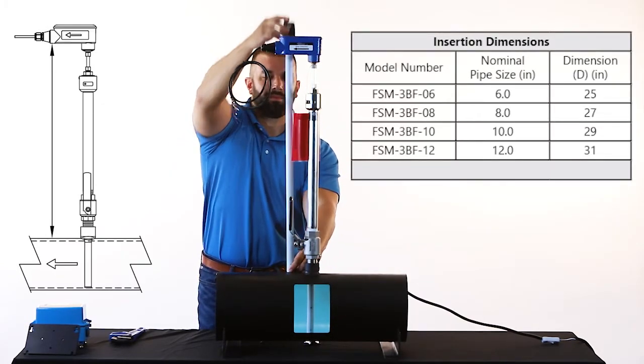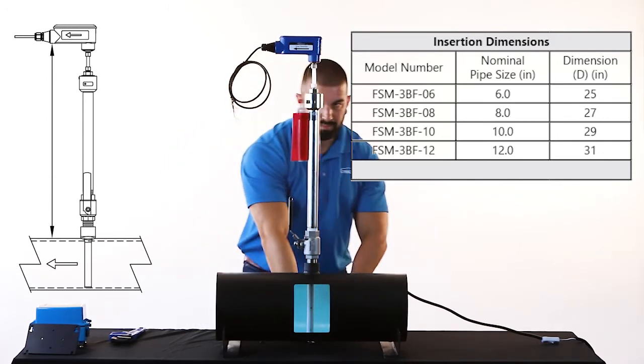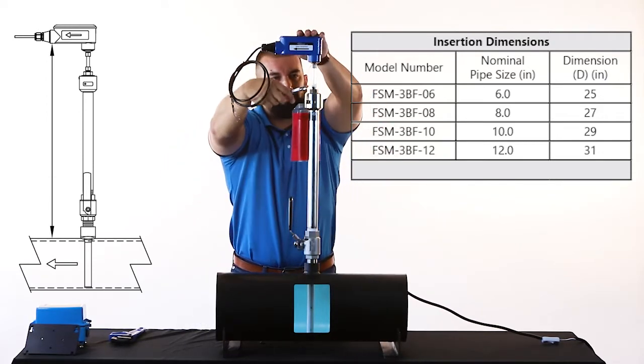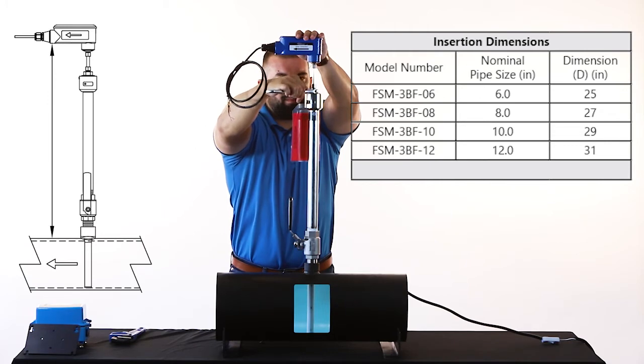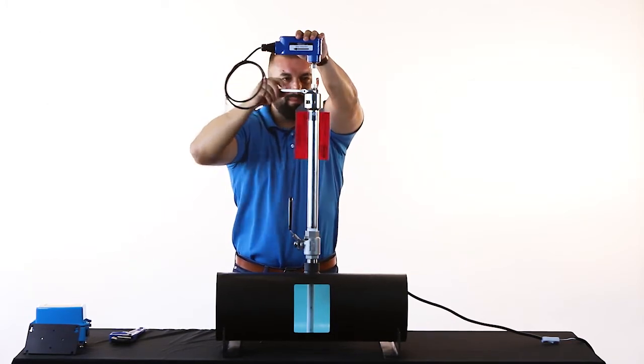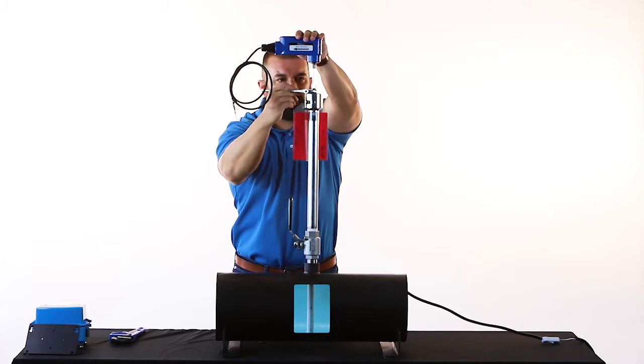Measure the distance from the top of the pipe without insulation to the bottom of the flow sensor enclosure. This distance should match the dimension needed for your specific size meter based on the table here and in your manual, confirming that the flow sensor has been fully inserted.